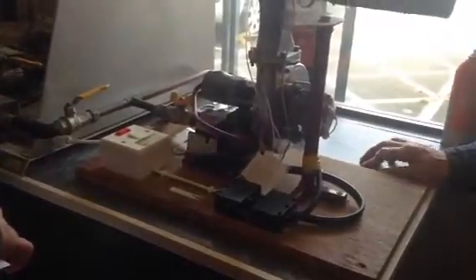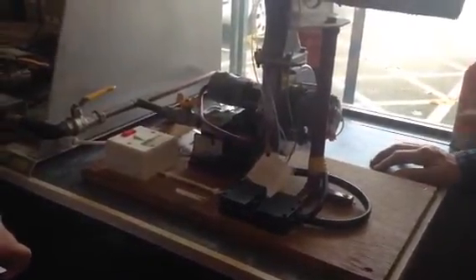It's purging itself now. So now what's happening, the fan's going, it's purging itself of any gas and air in the exchanger. It'll go through a purge cycle so that when it lights up it's not going to explode inside there basically. So purging the gas and air, then it'll go for ignition mode, power sent to that ignition probe, which is about 700 degrees, 704 degrees spark across there to ignite the gas. So now the gas and air is in the burner.